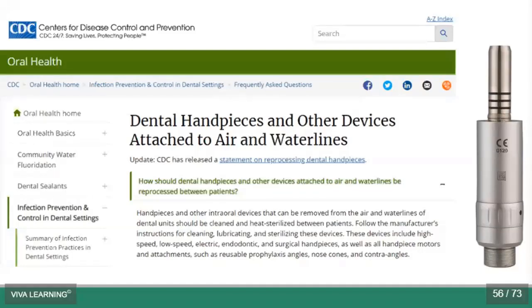This is straight from the CDC website. And it specifically says that handpieces and other intraoral devices that can be removed from air and water lines of dental units should be cleaned and heat sterilized between patients. And that includes high-speed, low-speed, electric, endo, and surgical handpieces, as well as handpiece motors and attachments, unless the manufacturer's IFU specifically says you can't.